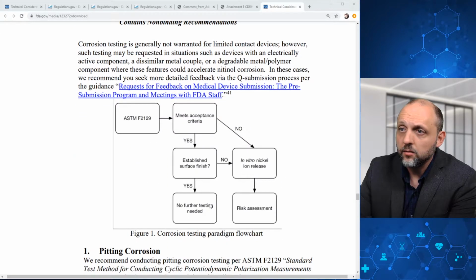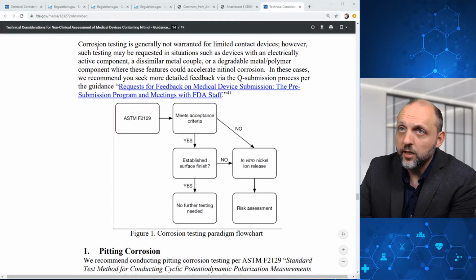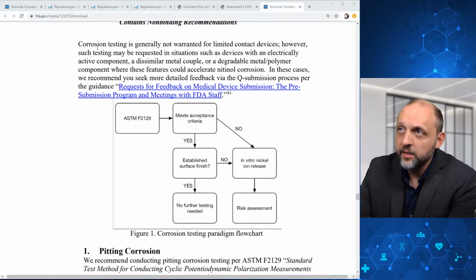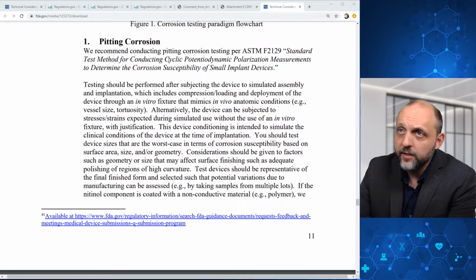And here we have this figure. And here FDA specifically calls out that corrosion testing is generally not warranted for limited contact devices. However, such testing may be requested in situations such as devices with an electrically active component, a dissimilar metal couple, or a degradable metal polymer component, where these features could accelerate nitinol corrosion. And again, FDA references the Q-sub process here. In terms of pitting corrosion, FDA recommends conducting testing per ASTM F2129. Testing should be performed after subjecting the device to simulated assembly and implantation, which includes compression, loading, and deployment of the device through an in vitro fixture that mimics in vivo anatomic conditions.